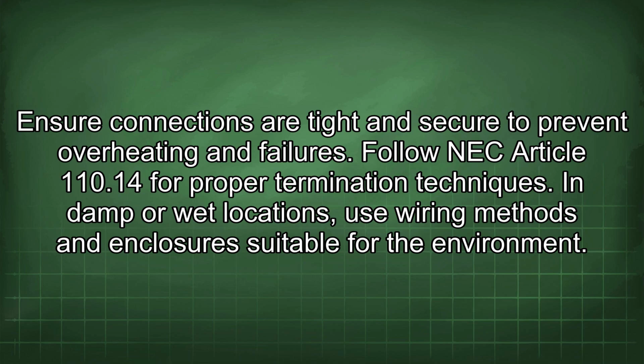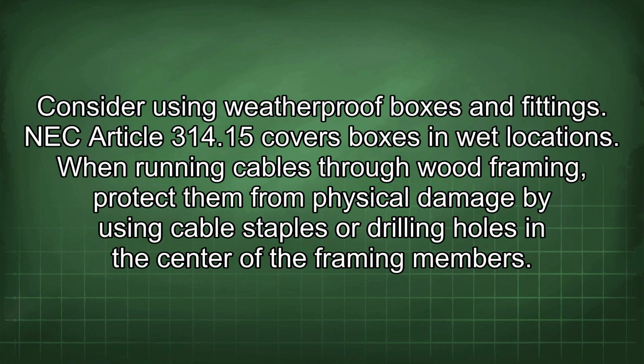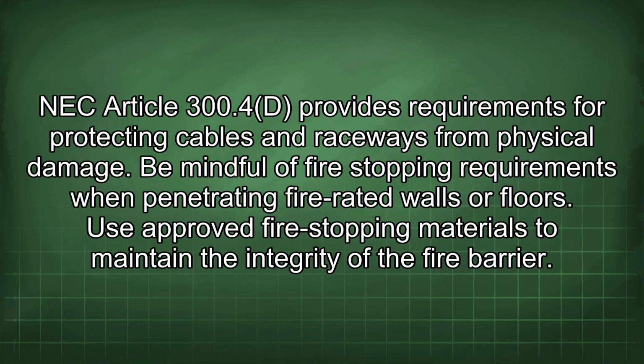In damp or wet locations, use wiring methods and enclosures suitable for the environment. Consider using weatherproof boxes and fittings. NEC Article 314.15 covers boxes in wet locations. When running cables through wood framing, protect them from physical damage by using cable staples or drilling holes in the center of the framing members. NEC Article 300.4(D) provides requirements for protecting cables and raceways from physical damage.